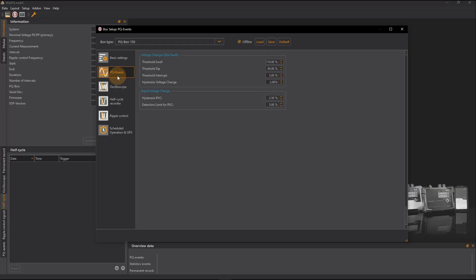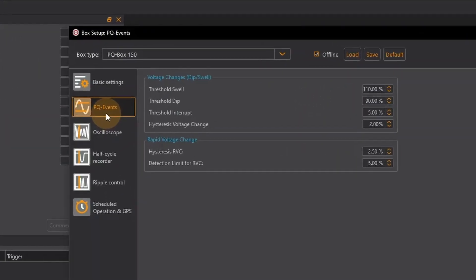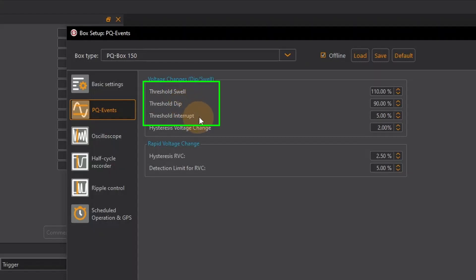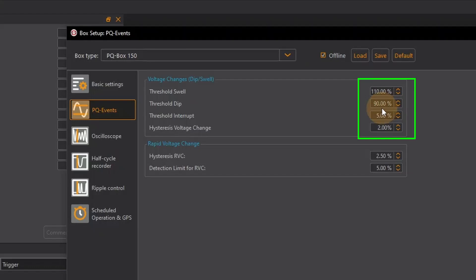Under PQ events I define the limits for voltage changes. For example the point at which a swell, dip or interrupt is detected. The values are given as a percentage of the nominal voltage. These values have a direct impact on the flagging of measurement data and cannot be subsequently edited for a recording that has already been completed. If the limit values are too strict the PQ box may flag all measured data and I will not see anything in the evaluation as long as flagged values are excluded.